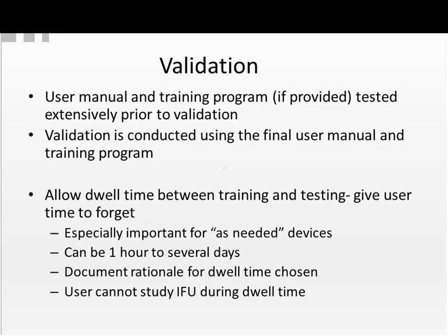You must document the rationale for the dwell time that you've chosen. During that dwell time, the user should not study the information for use. This is a very important point. The FDA focuses on the dwell time and the rationale for the dwell time.